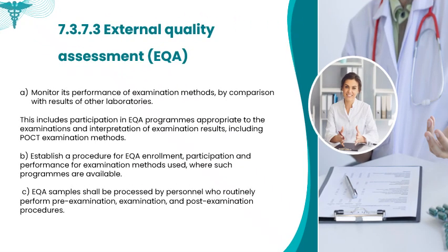External Quality Assessment, EQA. The laboratory shall monitor the performance of its examination methods by comparing results with those of other laboratories. This includes participation in appropriate external quality assessment, EQA, programs for examinations and interpretation of examination results, including point-of-care testing, POCT, methods. The laboratory shall establish a procedure for EQA enrollment, participation, and performance monitoring for all examination methods used, where such programs are available. EQA samples shall be processed by personnel who routinely perform the pre-examination, examination, and post-examination procedures.